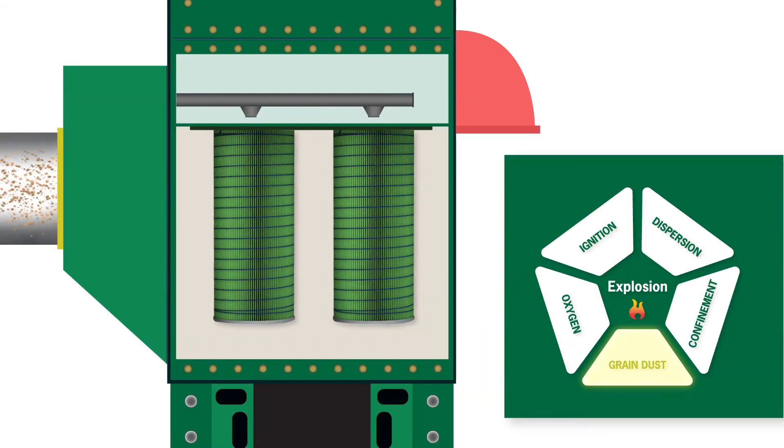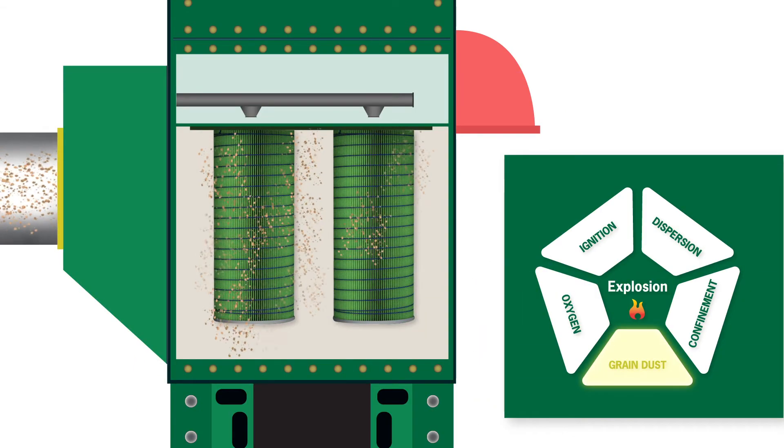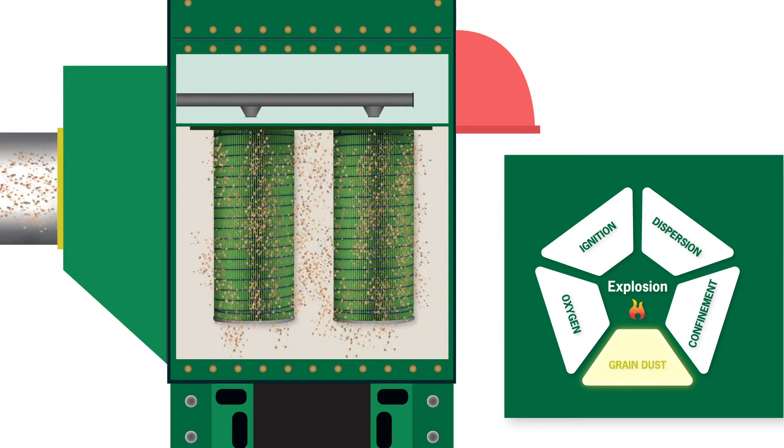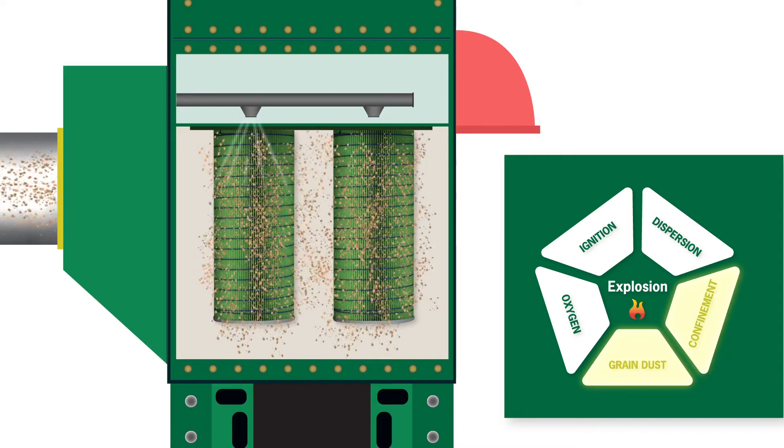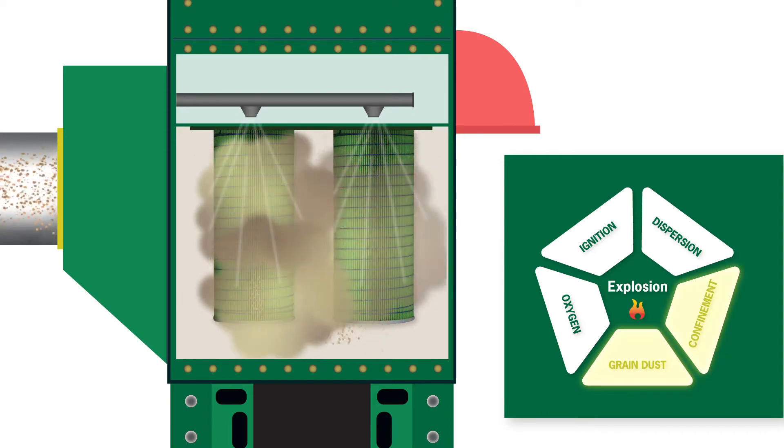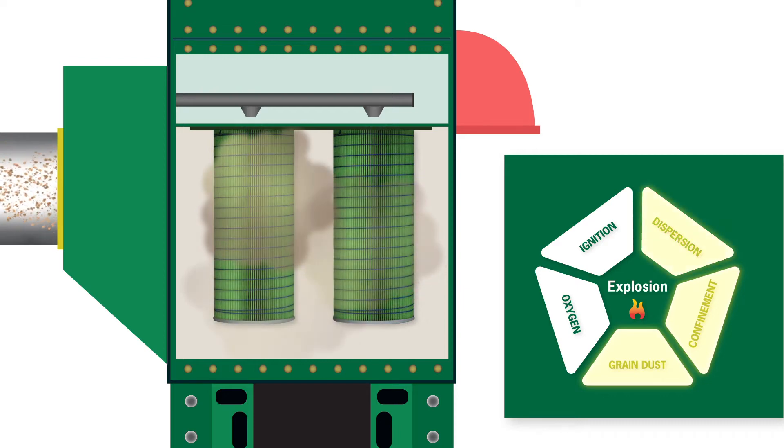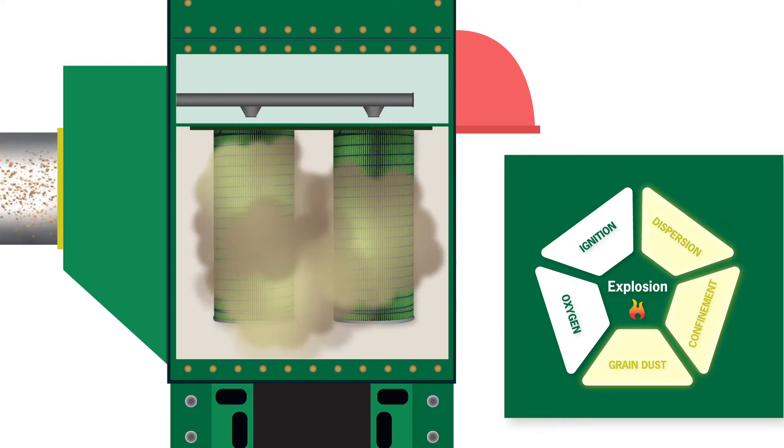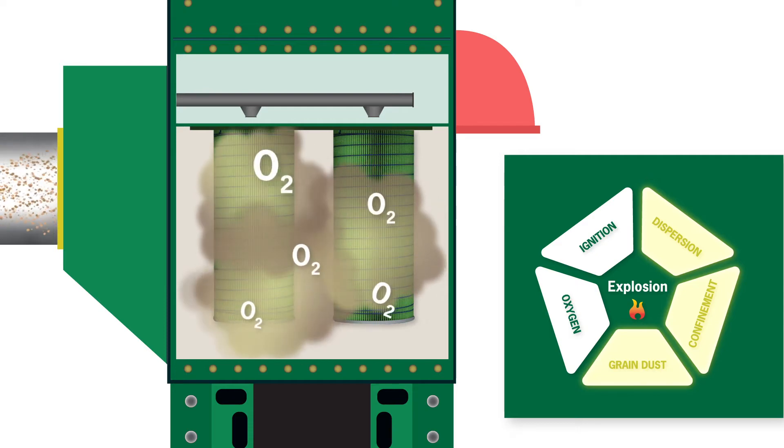Grain is the combustible dust, the fuel. As grain dust is pulled into the dust collector, you get confinement. When the compressed air pulse cleaners activate to blow dust off the filter cartridges, that's dispersion. The dust is dispersed into a cloud. When that happens, the dust is mixed with oxygen-rich air.